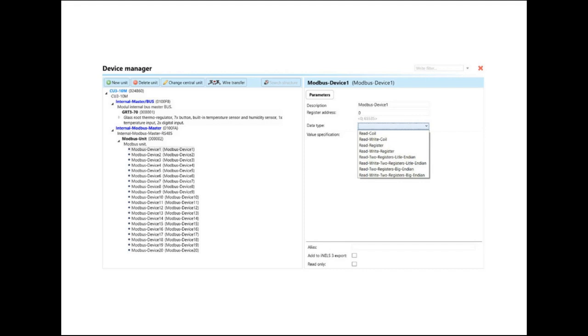So, for example, let's consider that we have a Modbus FCU, and it has register address 0 to turn on the auto mode. So you can use Modbus device 1, register address 0, and then you can select data type as read and write, and then you can send a command when we need to set the fan coil to auto mode.